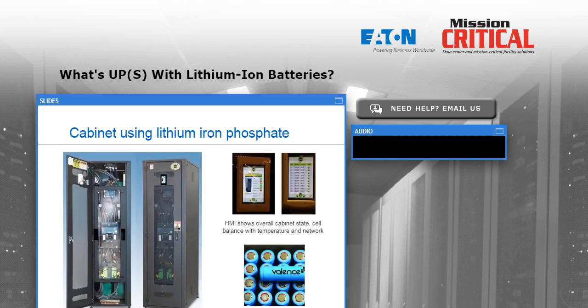Here is a cabinet using the lithium iron phosphate battery, and if you look closely on the cabinet on the left, with the green batteries in the bottom, they look like automotive batteries. They're about the same physical size and shape. But the good news is they only weigh about 20 pounds instead of 50 some odd pounds, and each one is 24 volts. And inside each little green enclosure is a whole bunch of lithium batteries. These ones in the picture on the right say Valence on them. That's the vendor. And these batteries are physically a little bit larger than AA batteries.